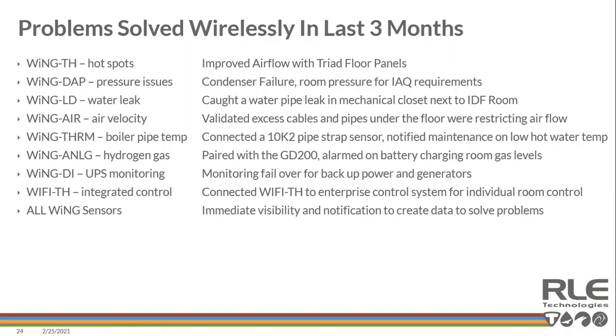Then we're able to solve some of those problems with our triad raised floor panels, performance air panels, allowing air to actually get at that data cage from 3 to 7 feet better than other standard panels out there. Another thing I just came across the other day, a partner of mine had the DAP sensor identify a condenser failure.